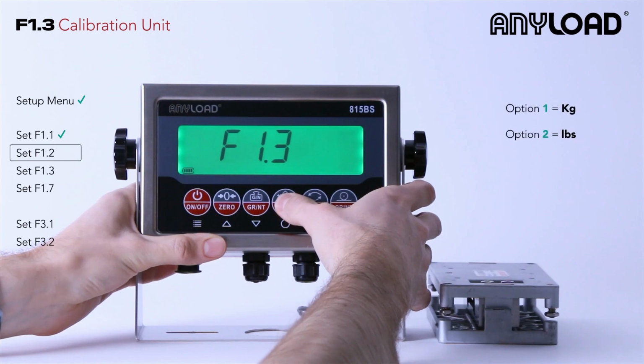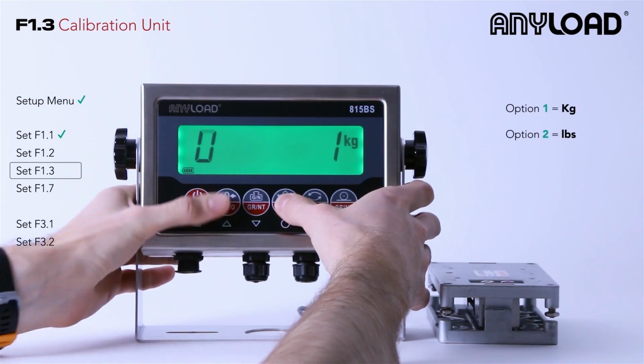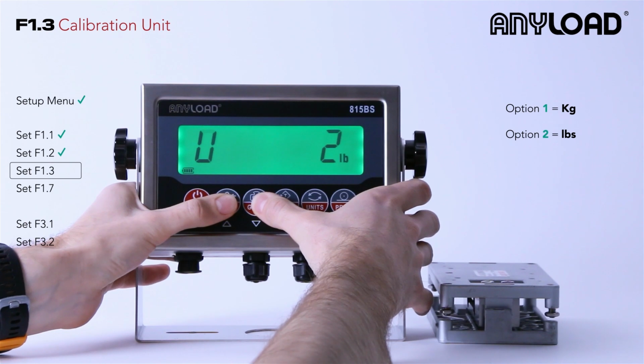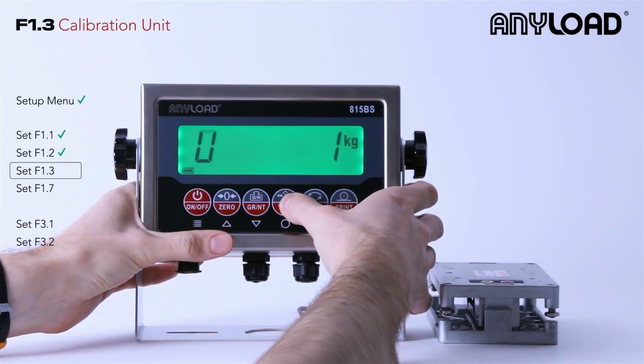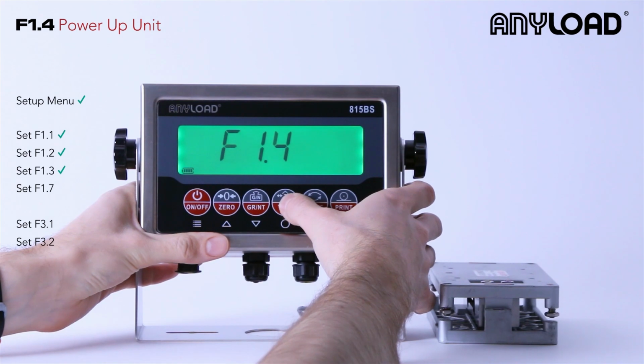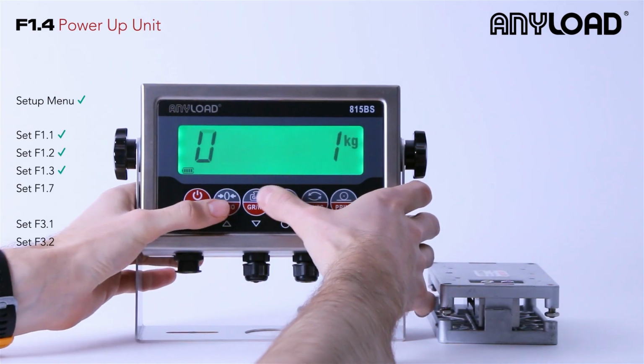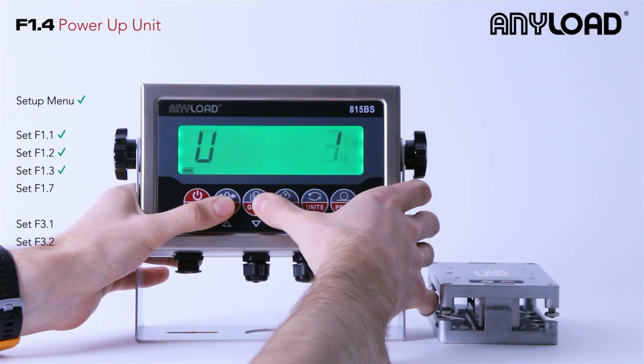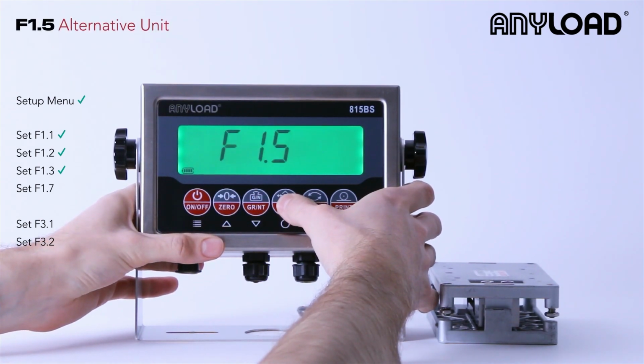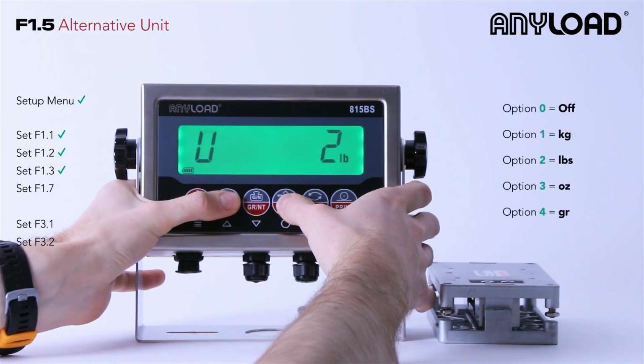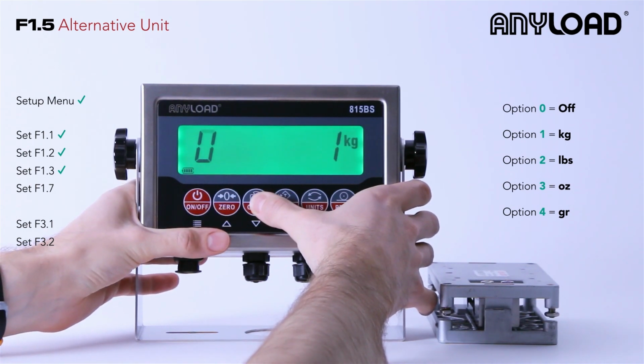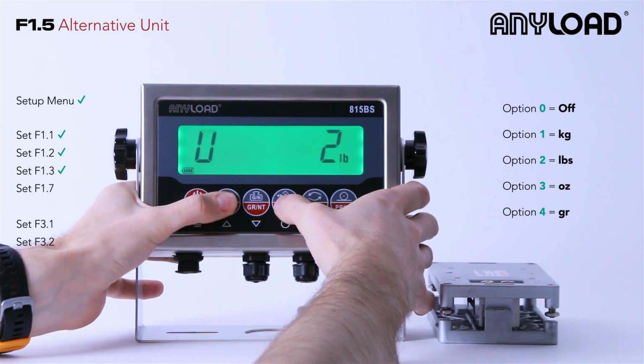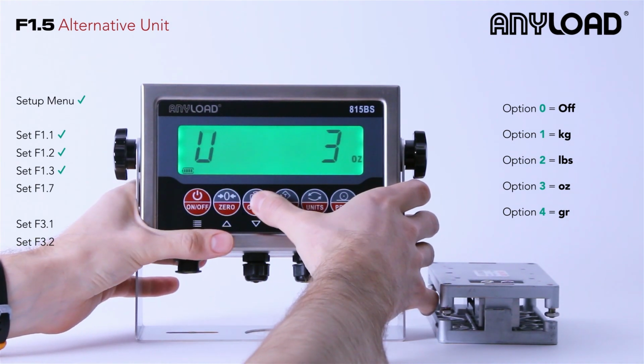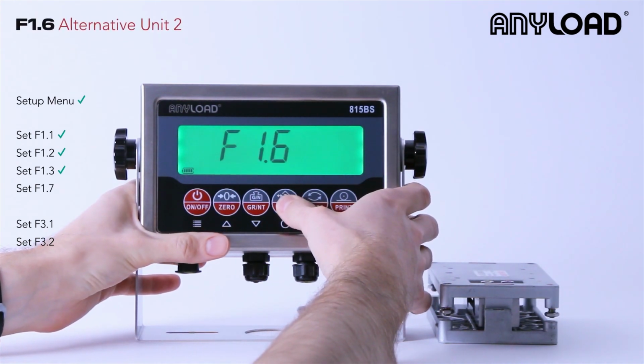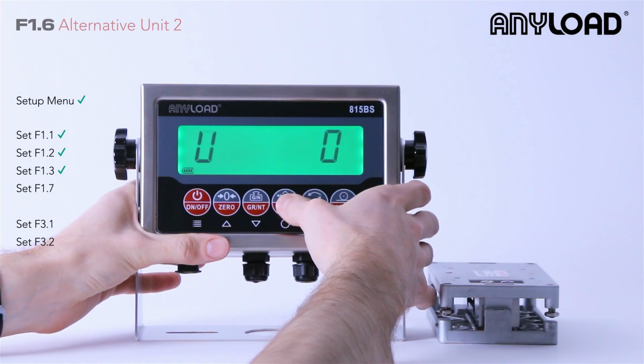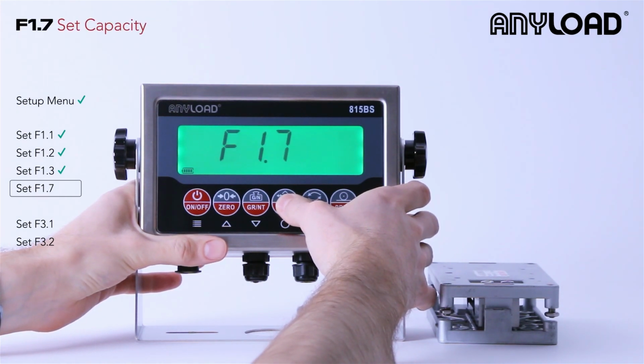F1.3 is our calibration unit. So we wanted this to be in kilograms, which is option 1, but you can also set this to pounds, which is option 2. Press tare to confirm. F1.4 is going to be our power-up unit. So this is going to be the unit you want displayed every time you turn on the unit. So we want ours to be kg. Your alternative unit is going to be if you want to view a different unit instead of kilograms. So you have a couple more options here, including ounces and grams. We're just going to set ours to 0, which displays nothing. Same for our second alternative unit.